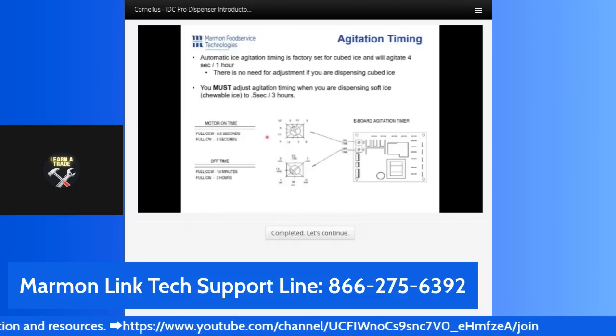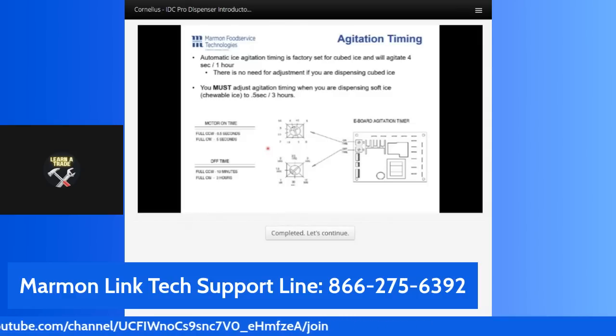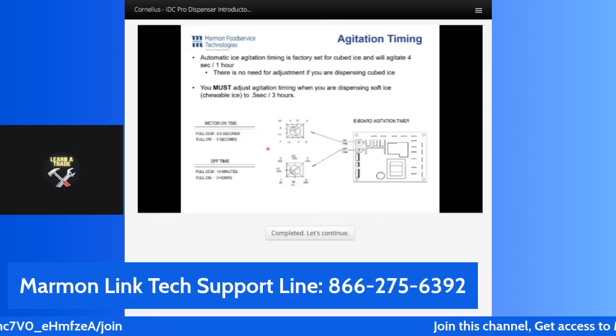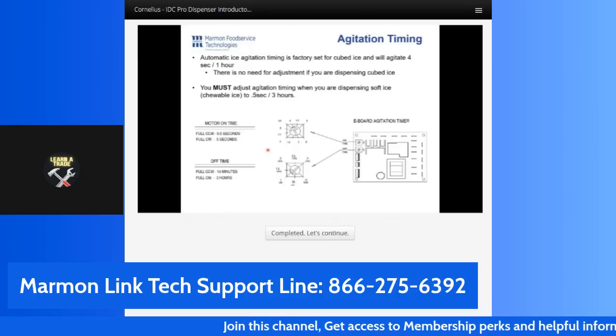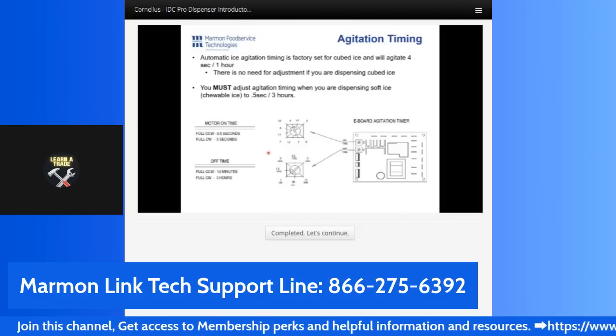As you can see here, the arrow's pointing to the 4 seconds and also pointing to the 1 hour. Now that's for cubed ice. That's what we assume that the unit is going to get put into. But there are a number of situations where soft ice or chewable ice is preferred and an ice maker appropriately installed on the IDC Pro to make that kind of ice. In that case there at install, these potentiometers need to be reset.